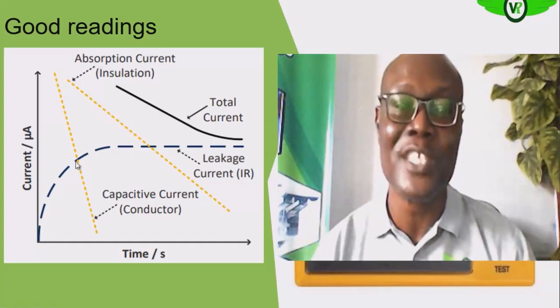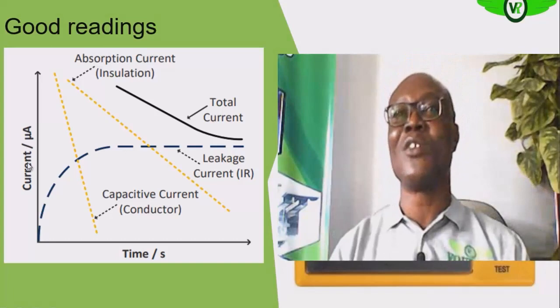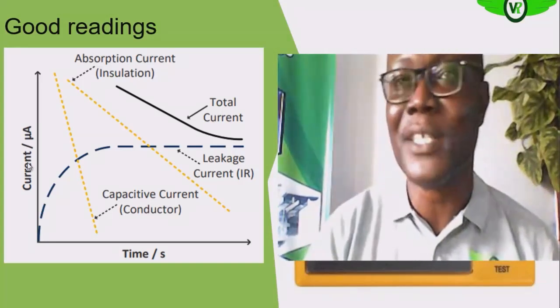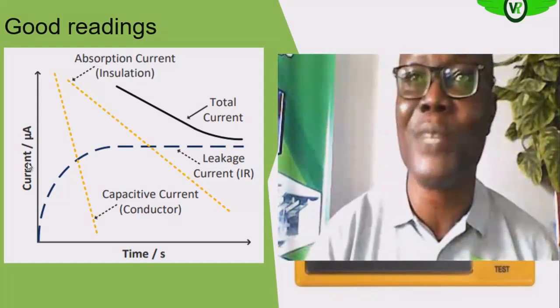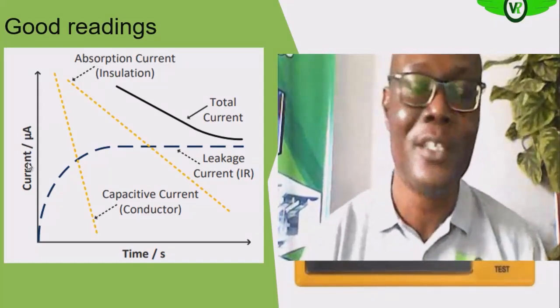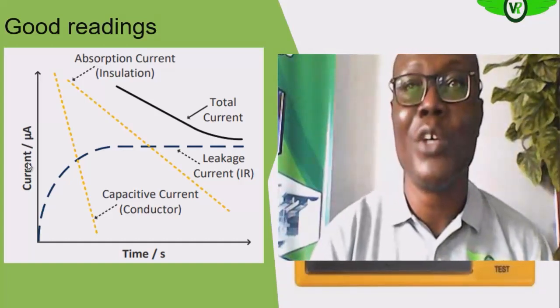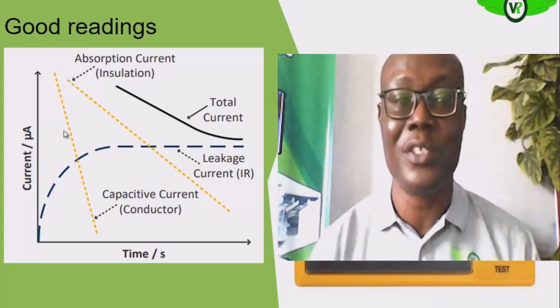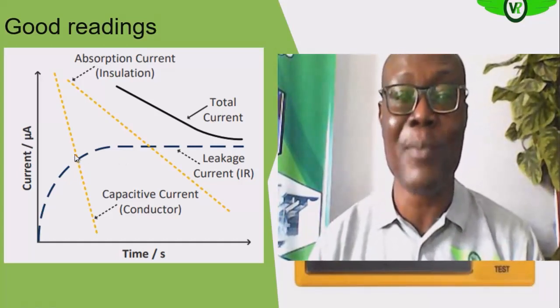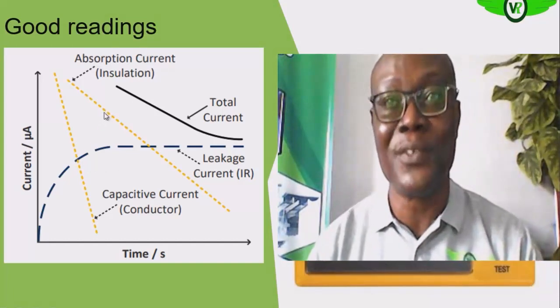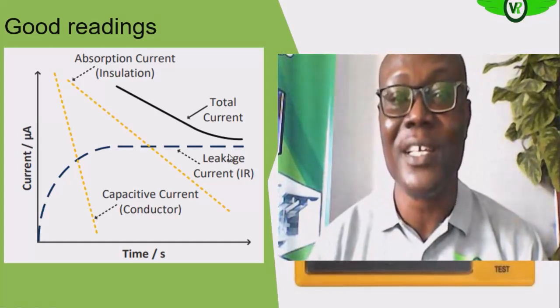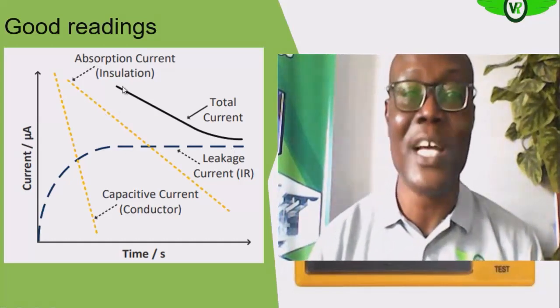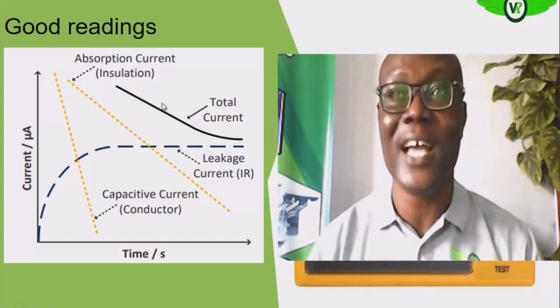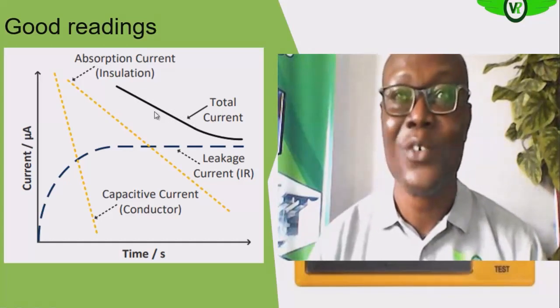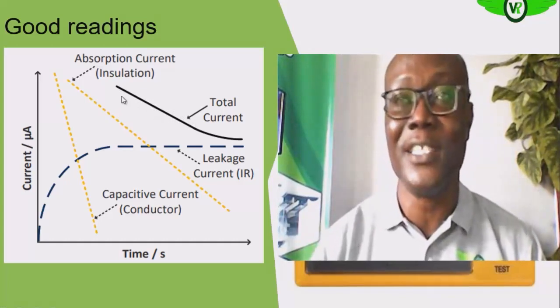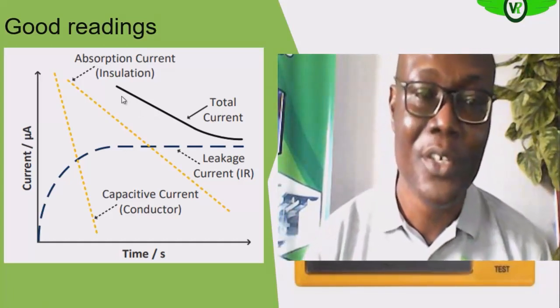Okay, so this reading that you take early, because most of us will make the mistake of just putting our probe, pressing the injection button, the test button. As you press to inject your voltage, you just record the reading out. So that is erroneous. Okay, because of what we are seeing now on the screen, you allow those two, the capacitive and the absorption current, to dissipate first before you take the reading, so that what you have is the leakage current. So you see that the total current is high when you rush to take it, because you have the leakage, the capacitive and the absorption current.